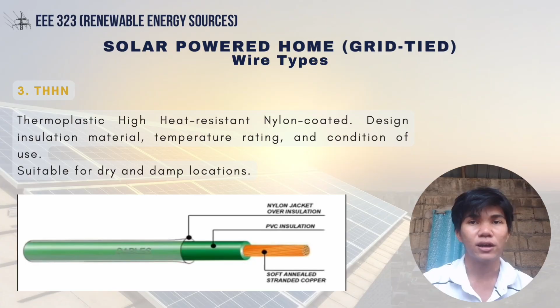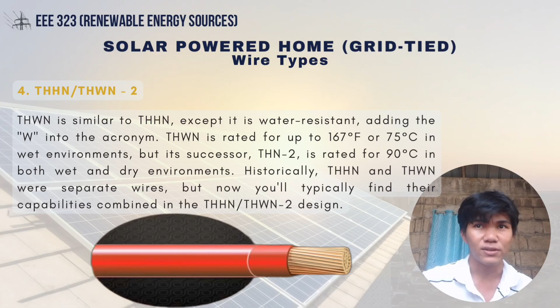THHN or THWN2 wire. Yung THWN, similar din siya sa THHN, except ito ay water resistant. So by adding the W into the acronym, THWN is rated for up to 167 degrees Fahrenheit or 75 degrees Celsius in wet environments. But its successor, THWN2, is rated for 90 degrees Celsius in both wet and dry environments. Historically, THHN and THWN were separate wires, but now you typically find their capabilities combined in the THHN and THWN2 design, meaning pinagsama na siya ng water resistant and heat resistant wire na kayang tumagal sa 167 degrees Fahrenheit sa mga wet environments and 90 degrees Celsius sa both wet and dry environments.